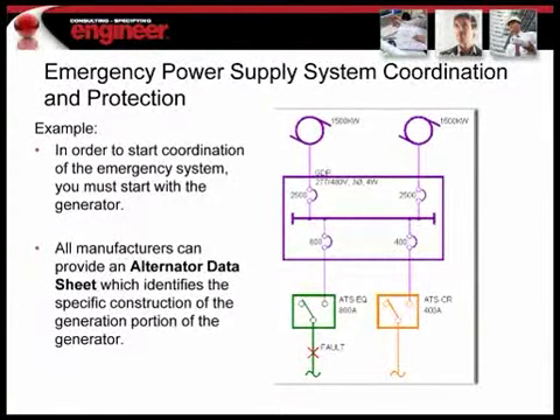So this is what I'm talking about. If there's an 800 amp ATS, the 800 amp ATS EQ, we want to make sure that that 800 amp breaker coordinates with the 2500 amp breaker serving the generators.